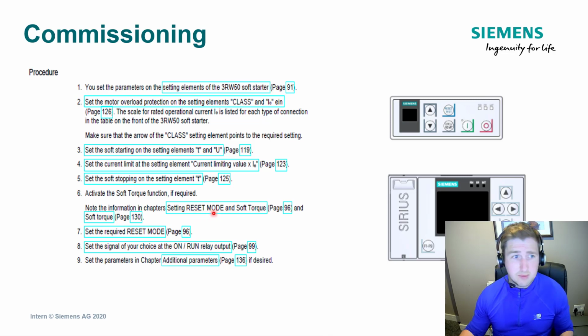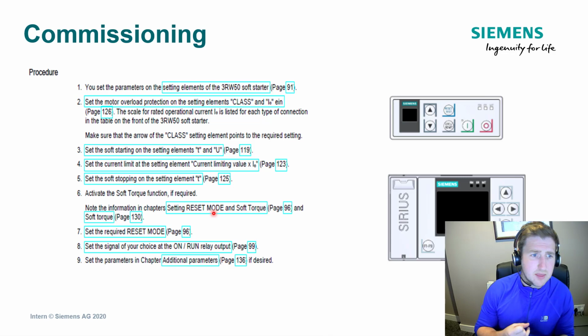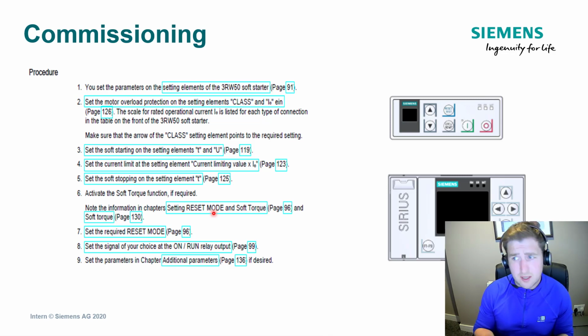So reset mode allows you to reset in 3 different ways. There's manual reset, so you have to manually acknowledge faults. There's remote reset, and then there's also automatic reset. So as soon as the fault's been cleared, it'll automatically allow you to restart the device without having to acknowledge the fault. So they're the main things that you need to consider when you're commissioning that particular soft starter.